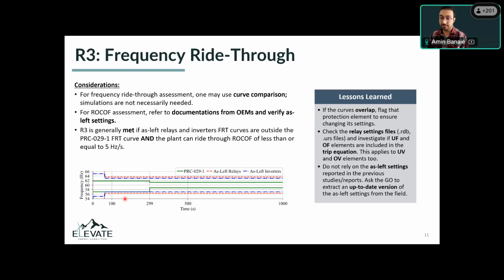The other thing is to check the relay setting files, and this is very important, to make sure that under frequency, over frequency, under voltage, and over voltage are included in the trip equation of that specific relay. And then you want to have the curves on this figure, because there are cases where these elements have been activated just for monitoring purposes, and they're not actually tripping the plant. So you want to check the RDB and URS files to make sure that they are in the trip equation.